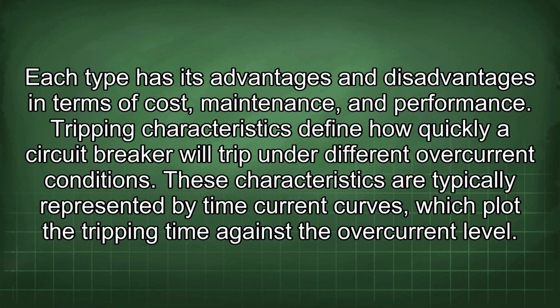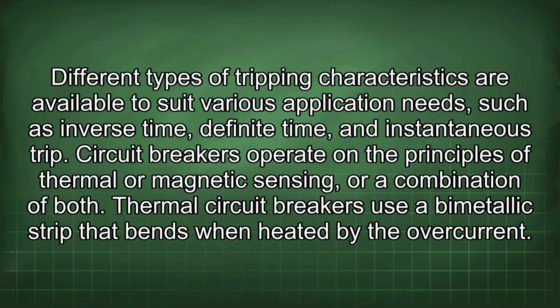Tripping characteristics define how quickly a circuit breaker will trip under different overcurrent conditions. These characteristics are typically represented by time current curves, which plot the tripping time against the overcurrent level. Different types of tripping characteristics are available to suit various application needs, such as inverse time, definite time, and instantaneous trip. Circuit breakers operate on the principles of thermal or magnetic sensing, or a combination of both.